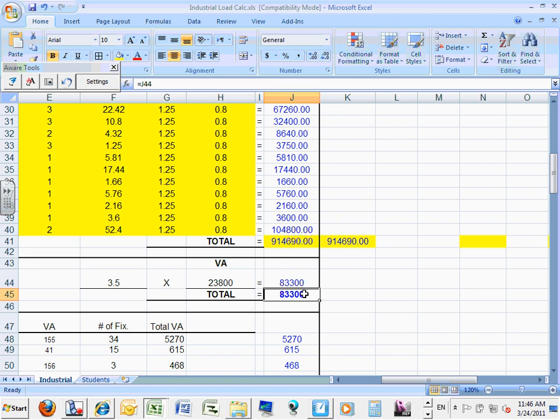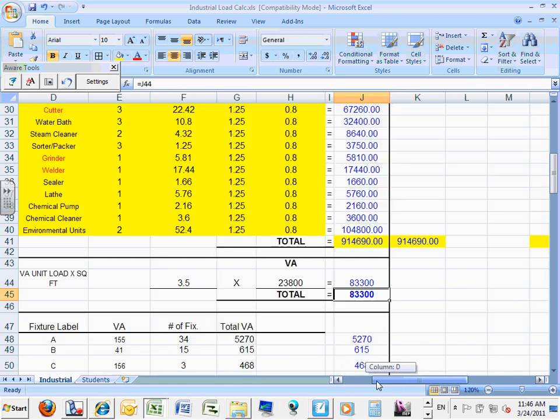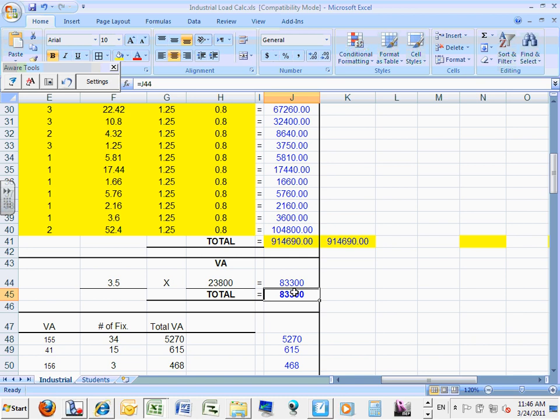Now, gentlemen, I want you to wake up here a little bit because it's a light. Here's what I want to do that my friend, the student who did that one, did not do, because we're doing it differently. Did you guys hear me? I'm going to multiply the continuous load right in here. So if you guys have room, put here 1.25. We're doing it slightly different. We're going to put the 1.25 right at this step. Why? Because it helps us carry it to the other lighting panel, guys.